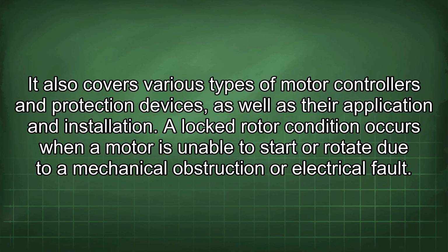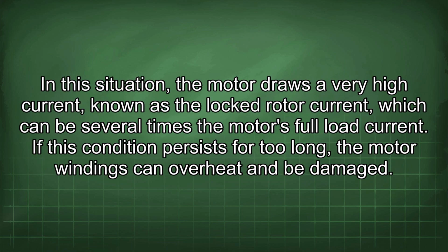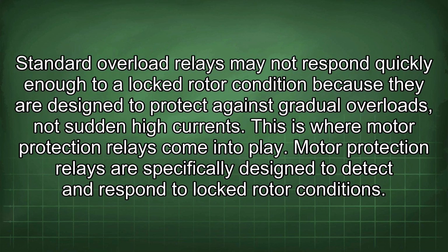A locked rotor condition occurs when a motor is unable to start or rotate due to a mechanical obstruction or electrical fault. In this situation, the motor draws a very high current, known as the locked rotor current, which can be several times the motor's full load current. If this condition persists for too long, the motor windings can overheat and be damaged. Standard overload relays may not respond quickly enough to a locked rotor condition because they are designed to protect against gradual overloads, not sudden high currents. This is where motor protection relays come into play.